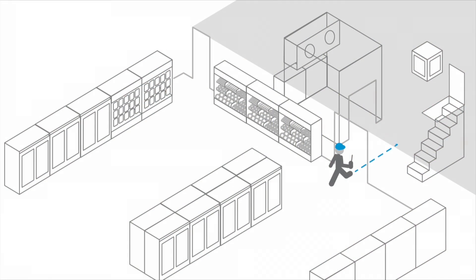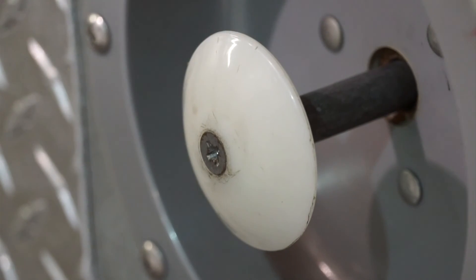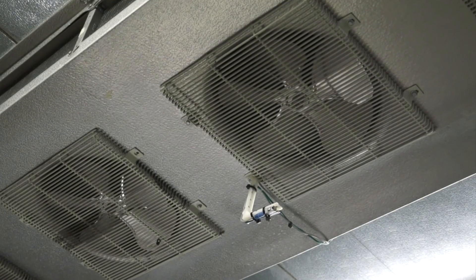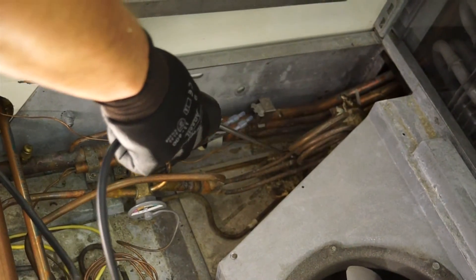You'll then want to check the back room walk-in cooler and freezers. Check the inside latch for safety and check for access to the evaporators. You'll also want to check for oil traces and stains.